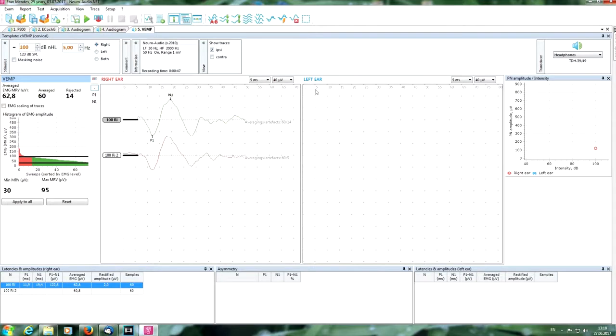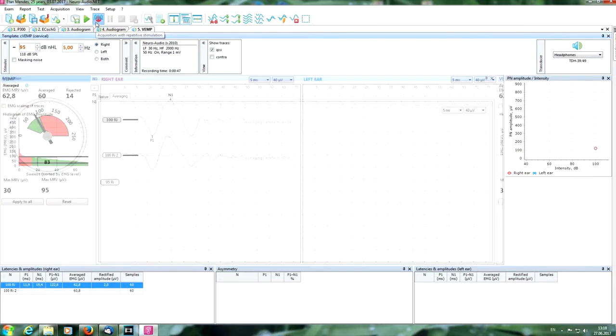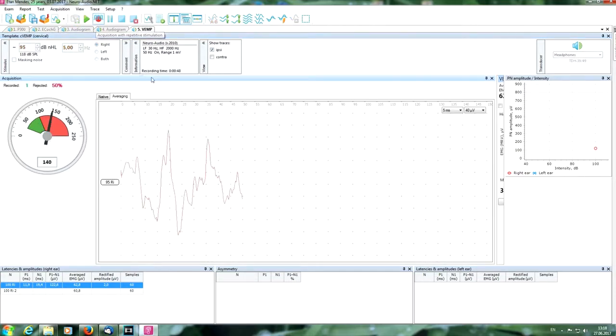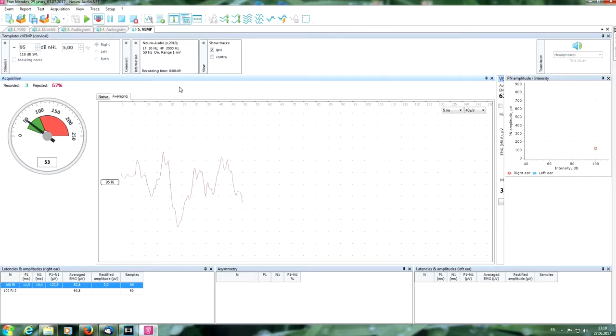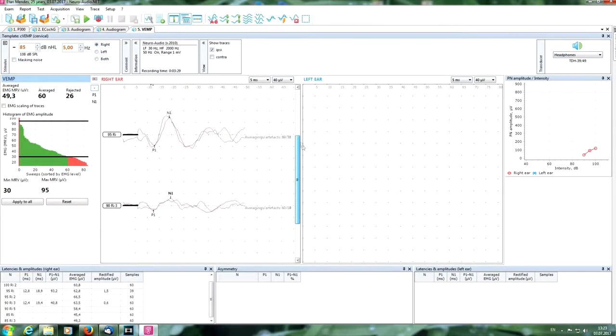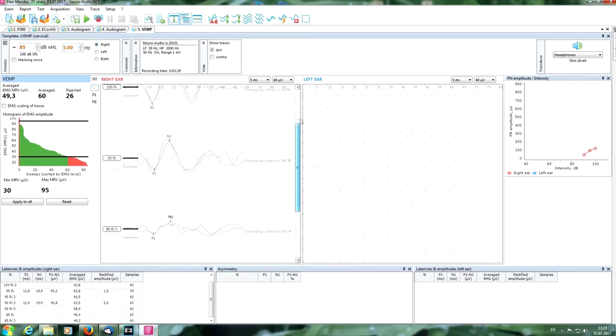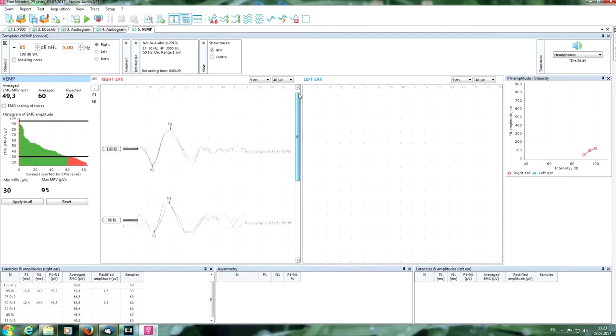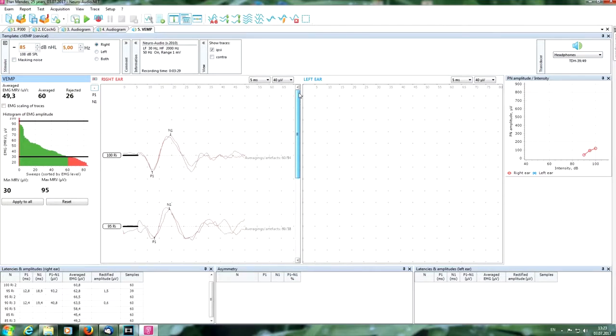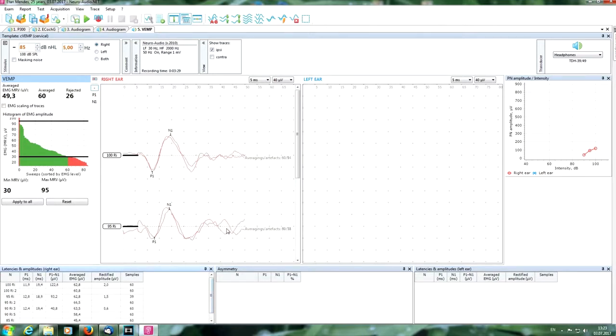We can decrease the intensity and try to search a threshold. Start the acquisition on another intensity. Okay, we get to 85 decibels. On 85 decibels we have no response. You can see the latencies and the amplitude in the tables, also averaged EMG rectified amplitude and samples quantity.